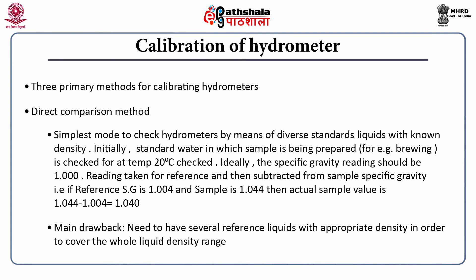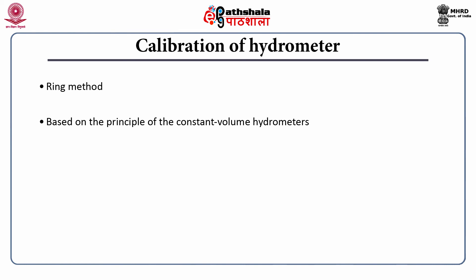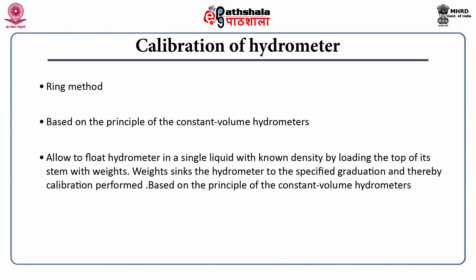The main drawback of the direct comparison method is that you need to have specific reference liquids with the appropriate density to cover the whole liquid density range — sometimes just taking water does not suffice. The second method is the ring method, which works on the principle of constant volume hydrometers. The hydrometer is allowed to float in a single liquid with known density by loading the top of its stem with rings as weights. You continuously add weights onto the stem and observe the change in graduation, thereby performing calibration.